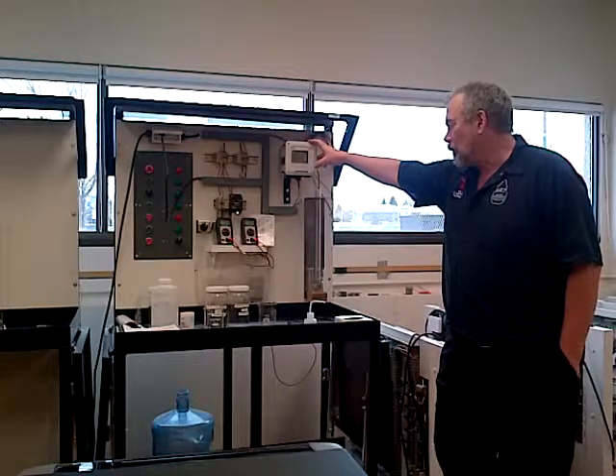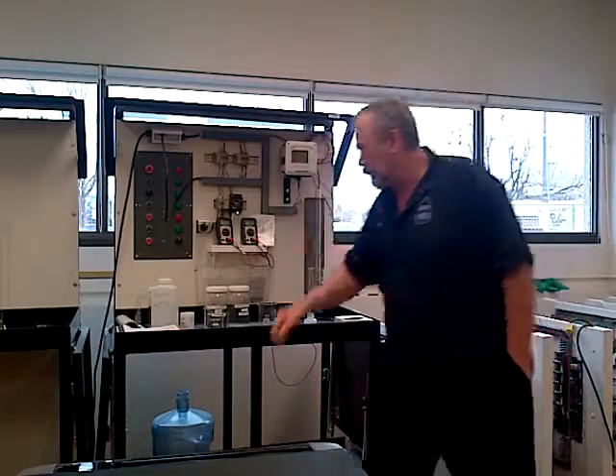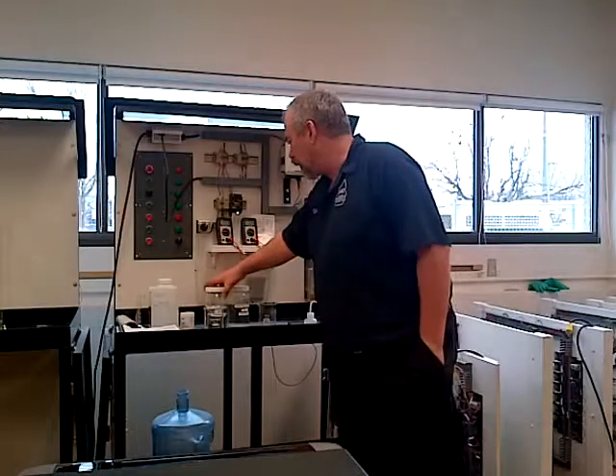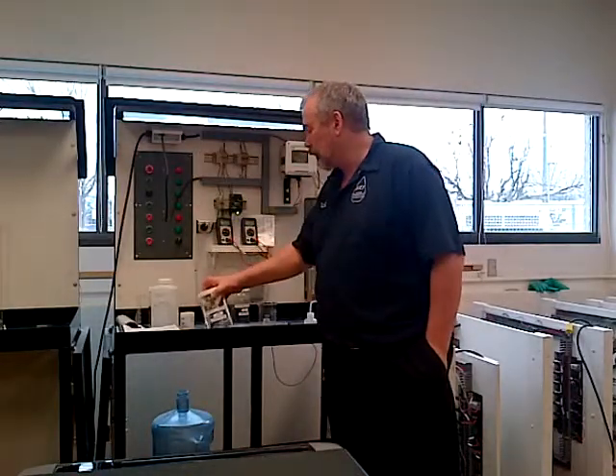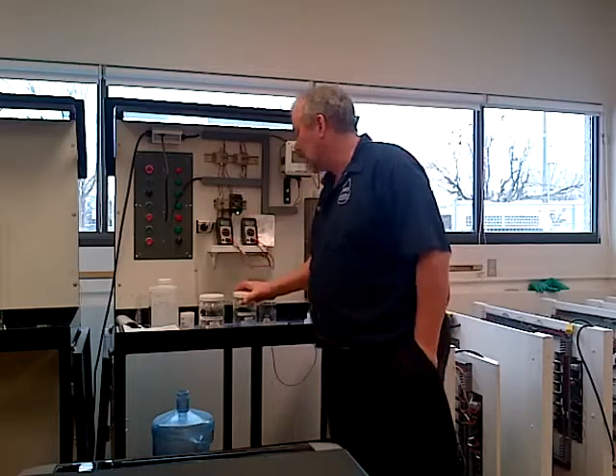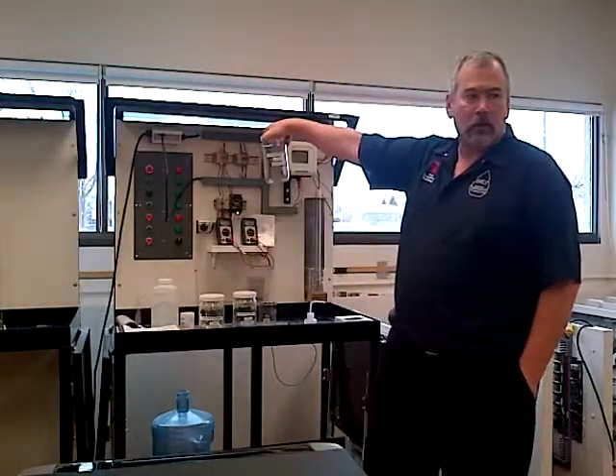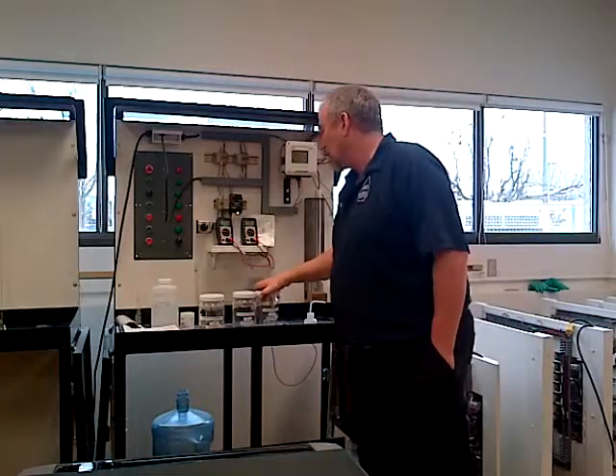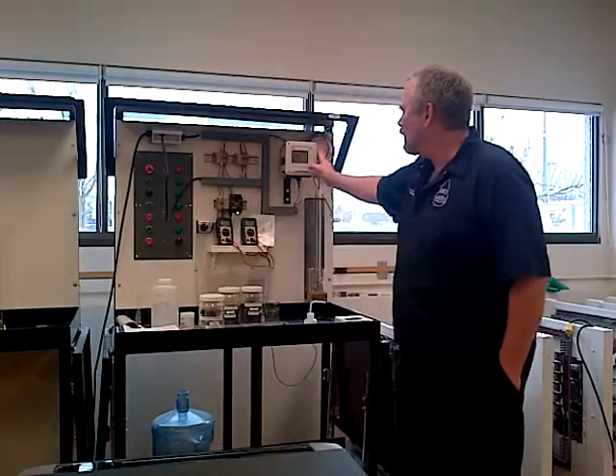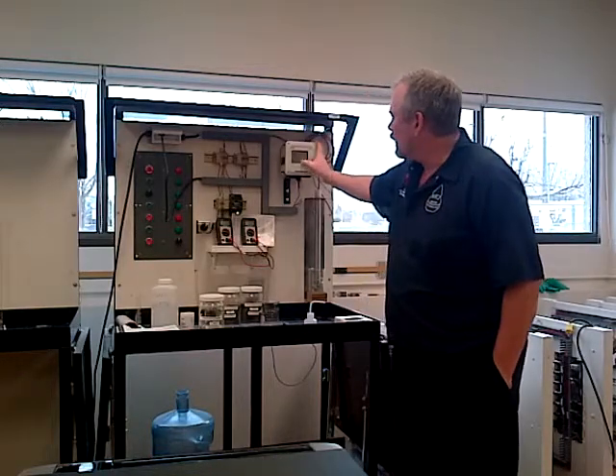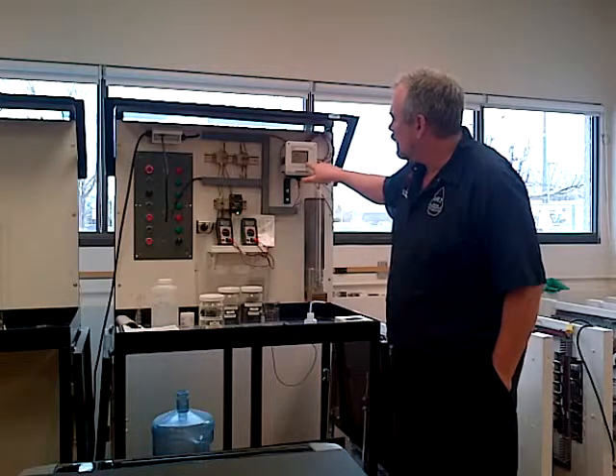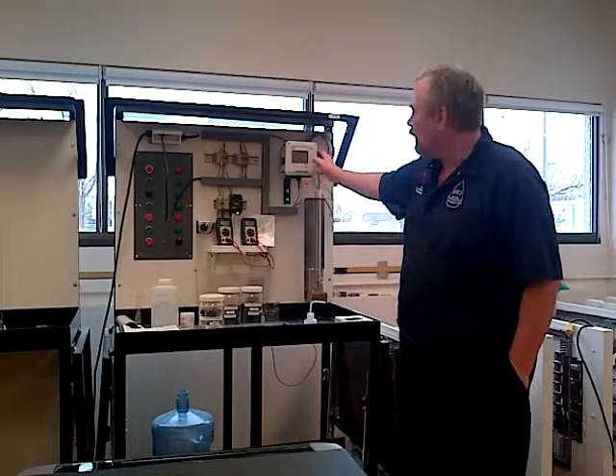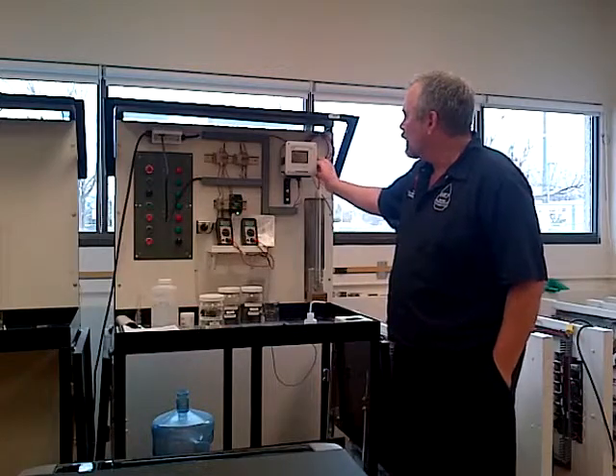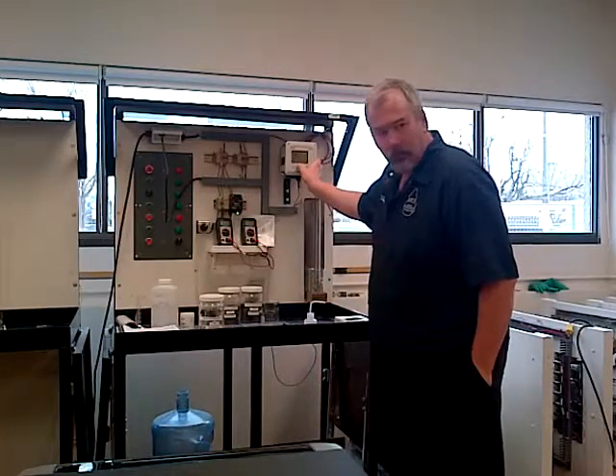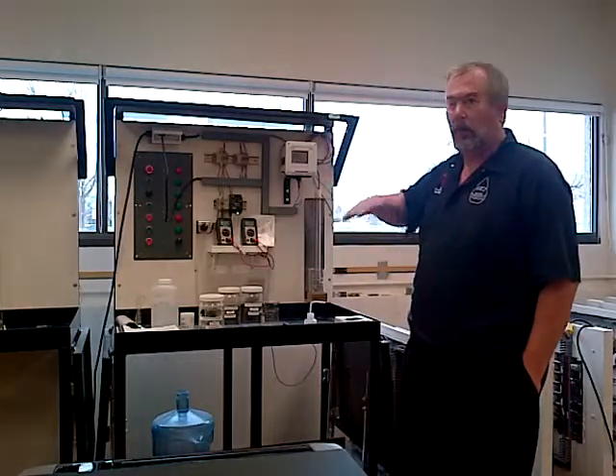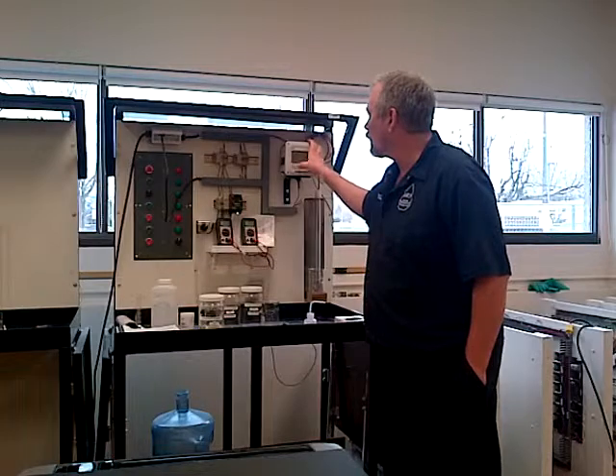Anyways, you're going to be measuring some standards. The standards are down here. At the beginning of the lab, I'm going to pour in, let's say, 1,000 microsiemens or 100 microsiemens or 1413, whatever is the standard. You're going to calibrate this, and it's incredibly simple, like I said. There's a bunch of numbers, and then they say what they are. So in the menu, it says calibrate. You can say select, and then it will run you through which standards it wants you to put in. I'm going to just go back to measure.